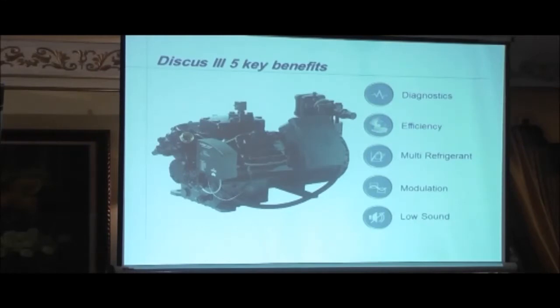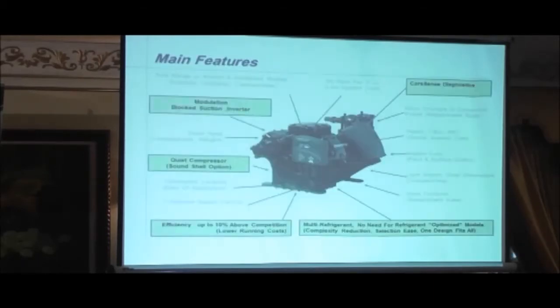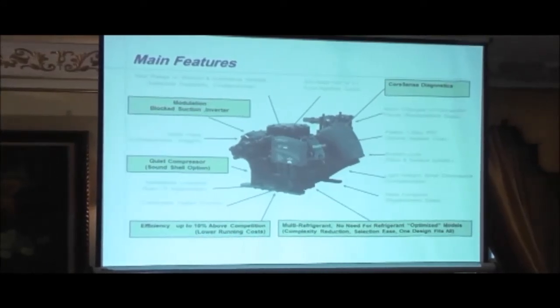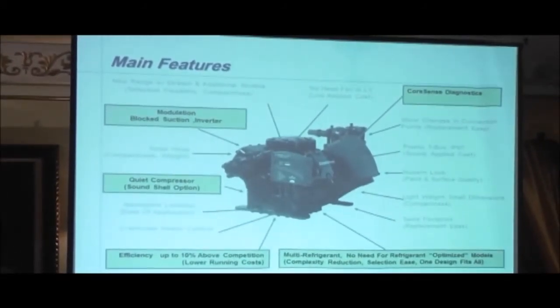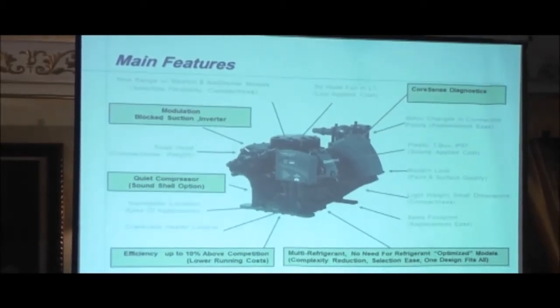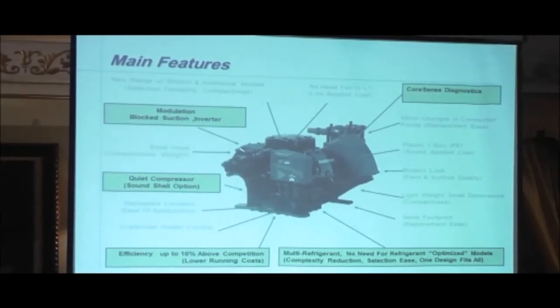We've got a couple of notes on modulation, and if sound is a benefit to you, then we've also made some strides in that as well. So what are the main features? Modulation: we will still be with the old technology in terms of blocked suction, but the motors, all of them, have been released with inverters if you choose to use inverters for capacity modulation. We've reduced the sound level of the compressor. Obviously we've increased the efficiency. We need to keep up with the new efficiency standards, either released through governing bodies or industry.